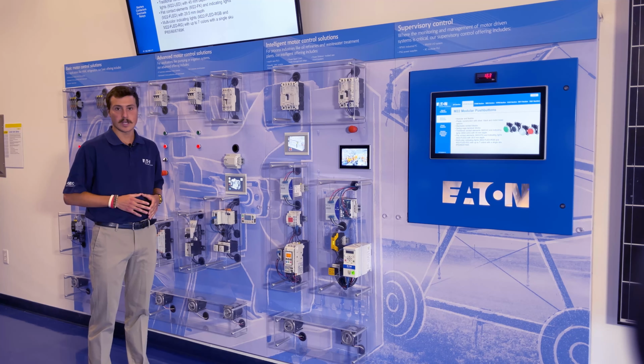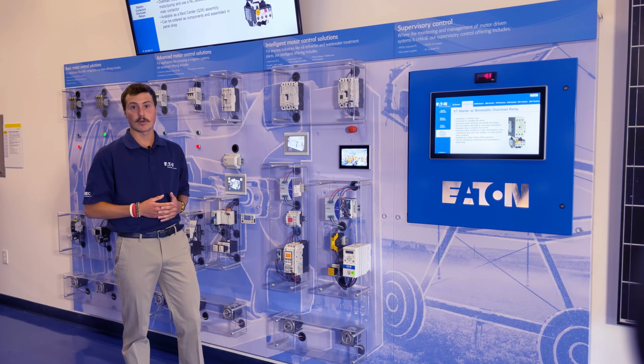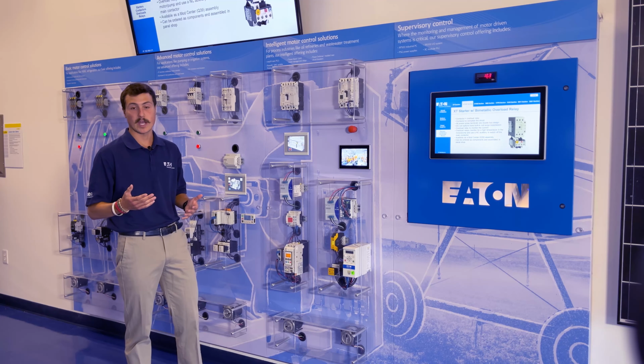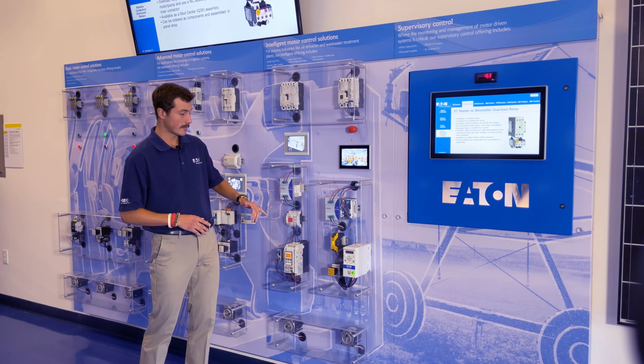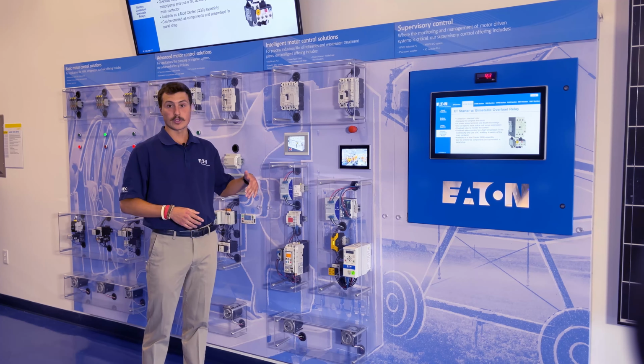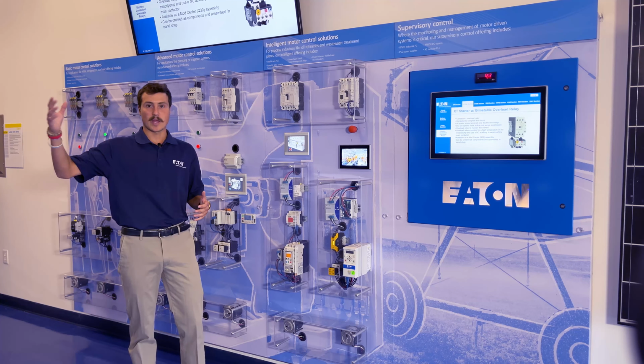In the second configuration, we have Eaton's S811 soft starter along with Eaton's easyE4 Nano PLC. The S811 soft starter we programmed to ramp up and ramp down the speed of the motor, which is really good in water pumping applications. The easyE4 Nano comes with 12 inputs and outputs, which can be expanded to a network of 188 I/O points. That's really good for things like lighting, energy management, pump applications, and HVAC.